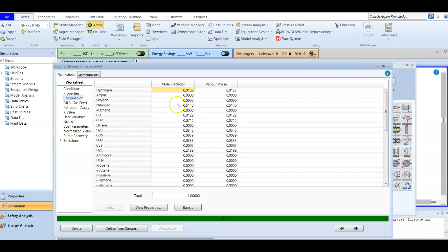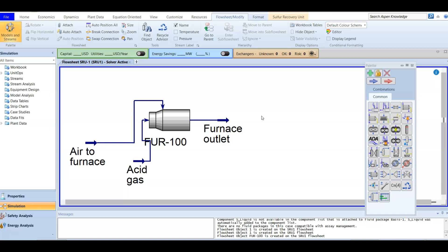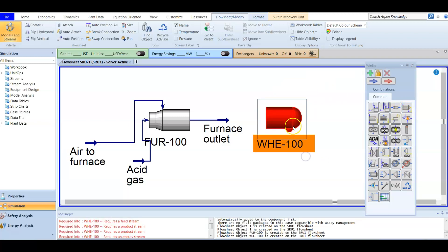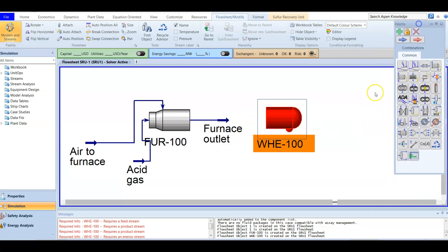The thermal step consists of three parts: the reaction furnace, the waste heat exchanger, and the sulfur condenser. Having added the reaction furnace, it's time to add the waste heat exchanger. In the SRU palette, the waste heat exchanger is a unit specifically designed for SRU. It is placed after the reaction furnace to cool the hot gas coming from the furnace outlet, and it also produces some liquid sulfur.